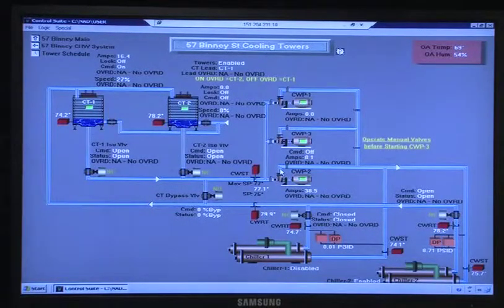But now they changed that as far as for the water flow reasons. Whenever the tower is initiated, or enabled, I should say, both isolation valves are open. So you'll see both of them open at all times. Which is this and this? No, the ones above it. Yes, those here. That's a normally closed position when they fail. These are normally open, right? So these are open when it's commanded on, so water can flow through.